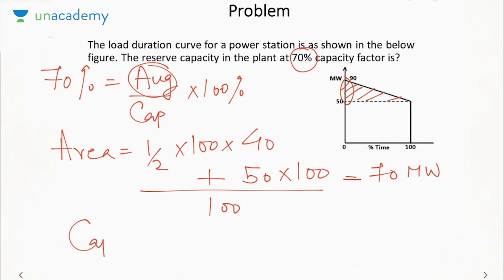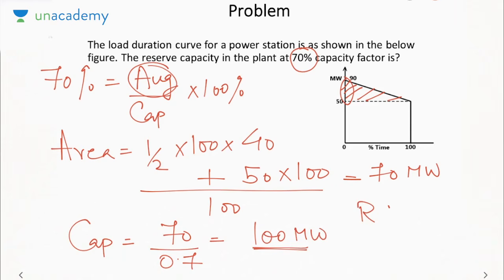Now we can find capacity. 70 by 0.7, because the capacity factor is 0.7, gives 100 megawatt. Reserve capacity is capacity minus maximum, 100 minus maximum. Maximum is 90 from the curve, so it is 10 megawatt. So that is the reserve capacity of the plant. So these sort of problems can be asked in the GATE examination for 1 mark only. These are pretty simple problems, but you must remember all the expressions. So now let us move on to the per unit system, as that is a prerequisite for the entire power systems course.